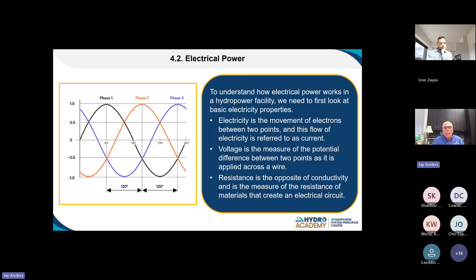Do we have meters that the operators can look at to do that? Or nowadays we have auto paralleling equipment, auto synchronization equipment we call it, that can allow us to actually connect our system totally automatically. The computer just says, all right, generator breaker closed, when all those conditions are met. So again, just a little bit of background there.